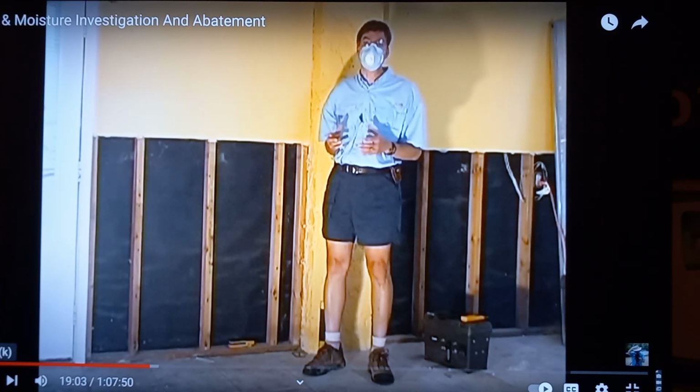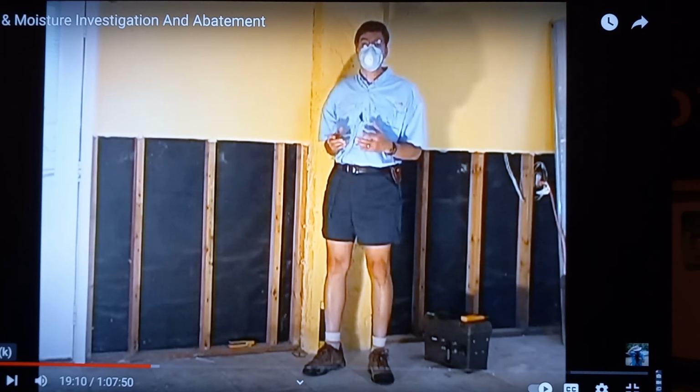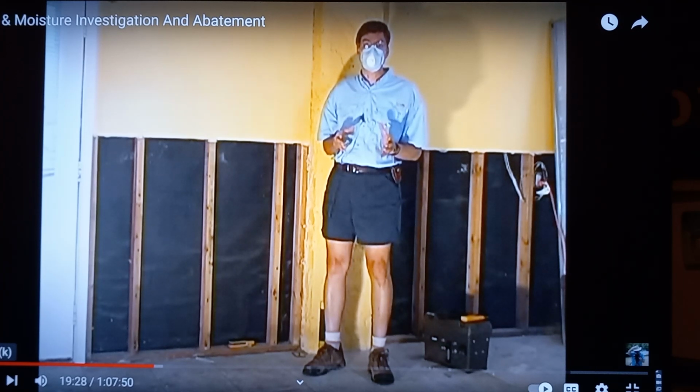A common problem is air conditioning. It's not just the lack of air conditioning that can create high humidity and favorable conditions for mold growth. It's also oversizing the units for a house or a building. This is because the air conditioning needs to run long enough to remove the moisture from the air. If the unit is oversized, it does what's called short cycling, and it comes on and goes off so quickly that it doesn't have a chance to remove the moisture from the air. It simply cools the air.